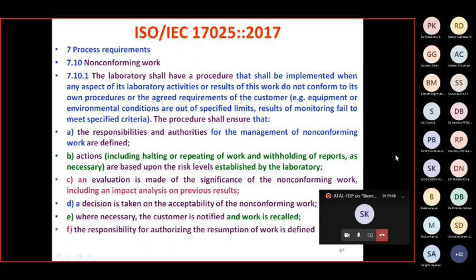An evaluation is made whether it is significant. For example, the operating calibration room temperature, instead of a 0.2 degree permissible upper level variation, went to 0.3. You can decide whether this will significantly affect the calibration activity done during that time. If so, you will repeat the calibration; if not, you will make a mention of it and still send it to the customer. So the evaluation is done by you on whether the deviation is going to significantly affect your results, and the decision is taken on acceptability of the NC work, and the customer is notified when the work is recalled.